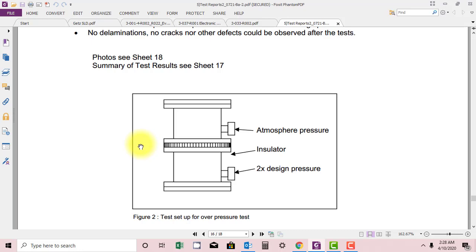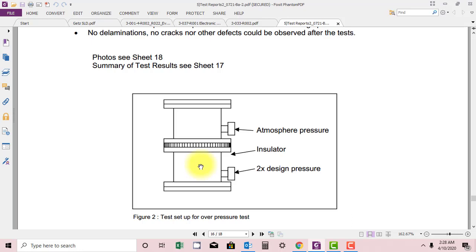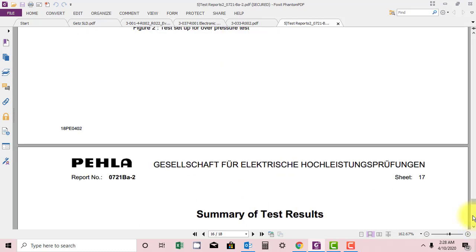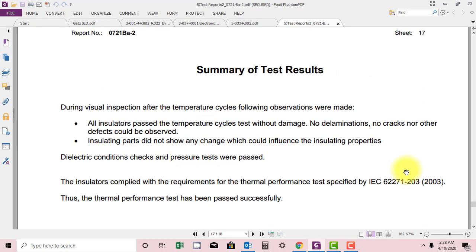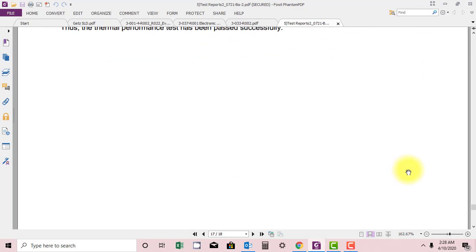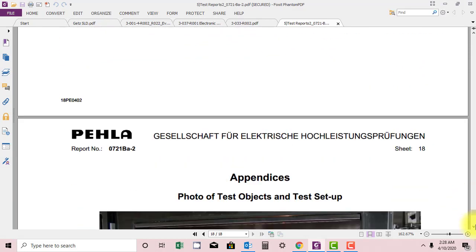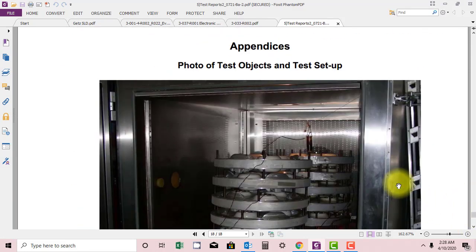in a GIS there are compartments and in between the compartments there is a barrier. So this barrier should withstand two times the rated pressure of the compartment. So they are applying at one side this much pressure and it should withstand for 72 seconds.